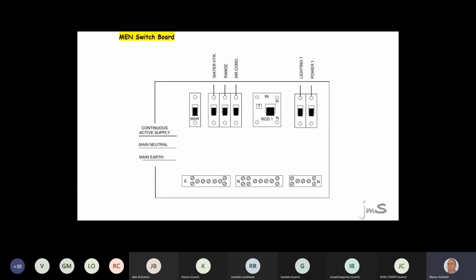Why is the DB not connected, where there's no link between the neutral and the earth? Sorry, repeat that again. Why is there no link in the DB? Because earth neutral. Okay, I'll show you now. If I bring in earth to earth bar, 2 screws. If I bring in link, 2 screws. If I bring in my neutral, 2 screws. You all agree with that? Yeah. Right? Now, active comes in, and then you can loop it to the other parts.